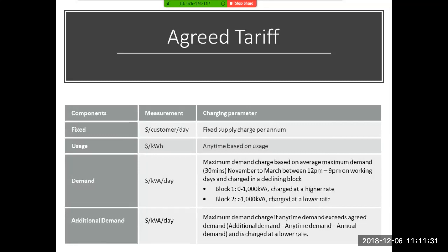And again, when we're talking about half-hour increments, it's important to realize that, let's say your electricity has peaked at 1,000 kVA for 15 minutes. Remember, it's an average over half an hour that this gets measured. So you've peaked at 1,000 kVA for 15 minutes. Now let's say that the next 15 minutes is down to zero. What that essentially means is that the average of that half-hour block is 500 kVA.